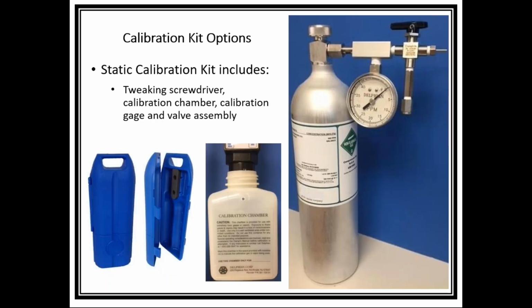The static calibration kit is slightly different. Delphian has always been concerned about the user as far as two things: the danger level in applying toxic gases to your sensor, and also the cost of performing a calibration. A lot of the competitors still use ampules. Ampules could be $8 a piece for a calibration. The beauty of our static cal kit is that you can get up to 400 calibrations out of a cylinder, which is quite a few calibrations when you think about the cost of performing a calibration.